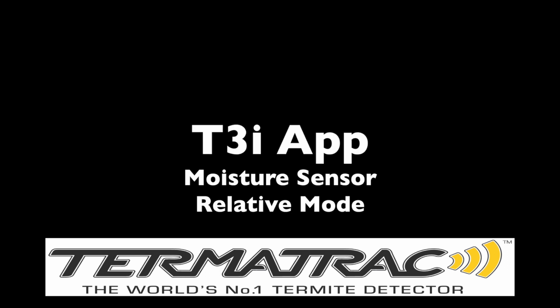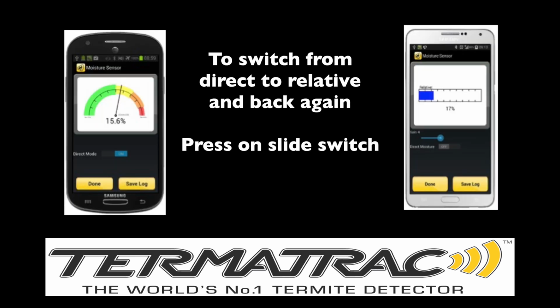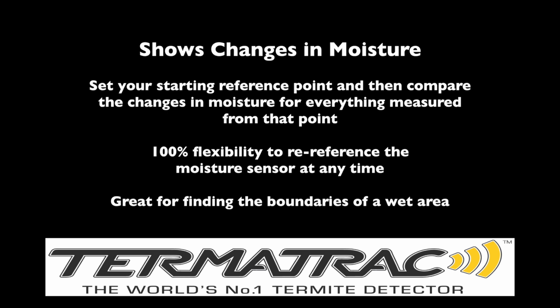Now let's take a look at the relative mode in the moisture sensor. To switch from direct to relative and back again, press on the slide switch seen here. The relative moisture meter will show you changes in moisture from a set reference point. It is 100% flexible to change this reference point in each area you are using it. It clearly shows on the display from each reference point whether you've got more or less moisture in an area.